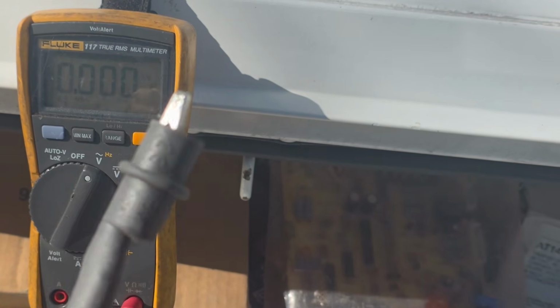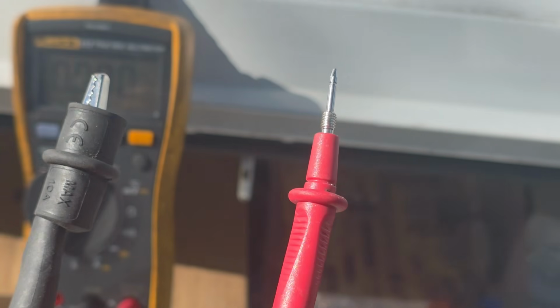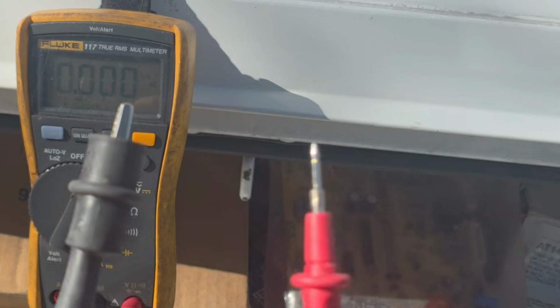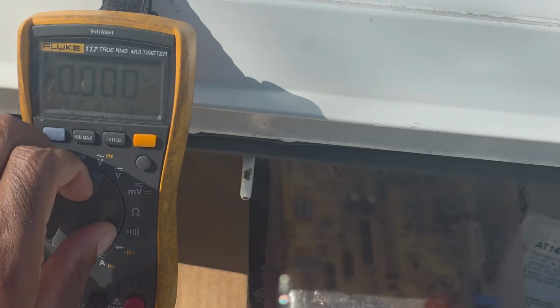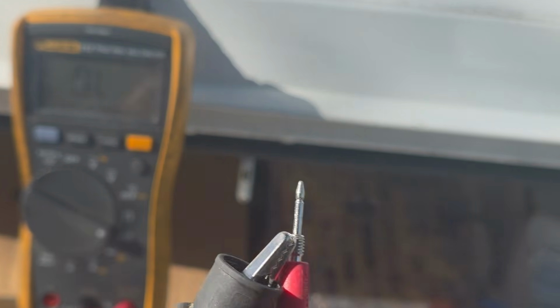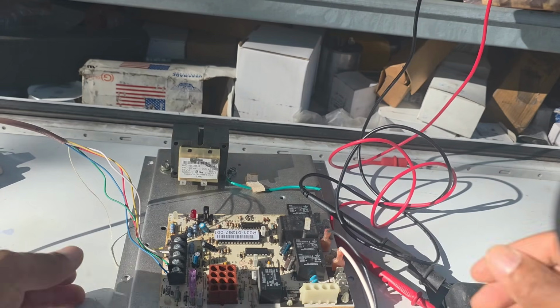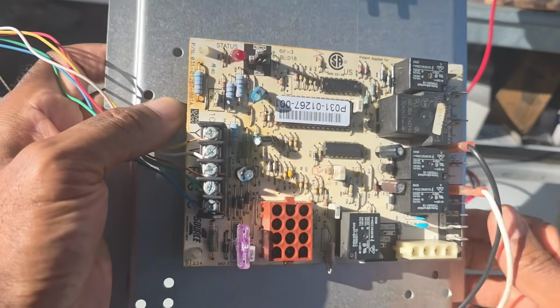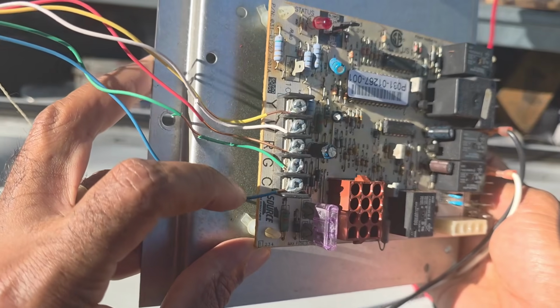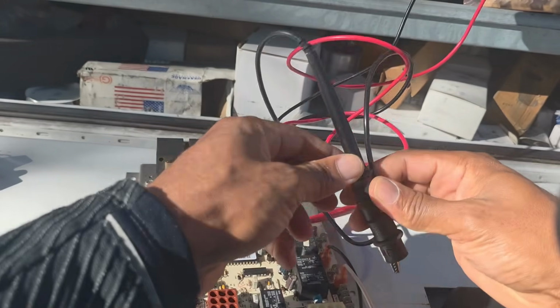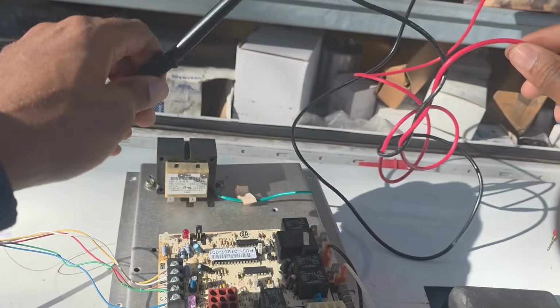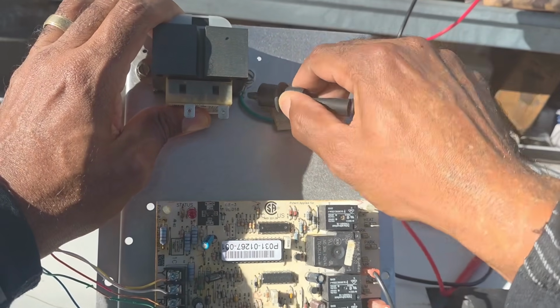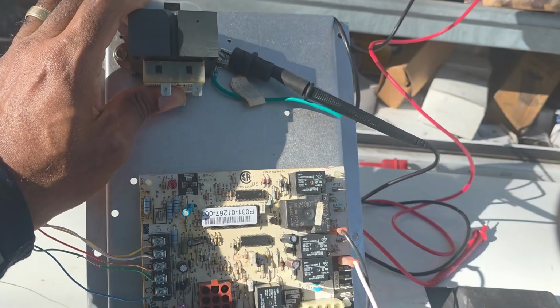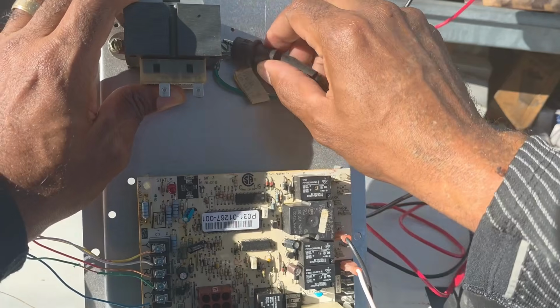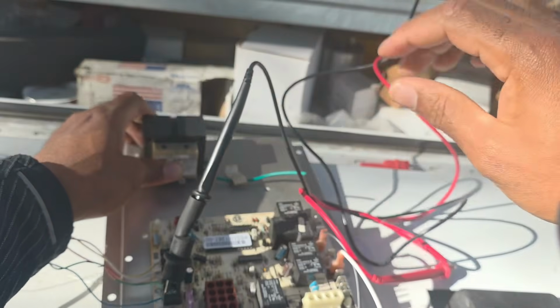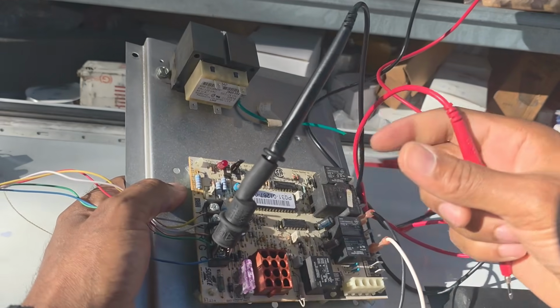All right, so now we have our pivot foot, and we have our lead that we're going to chase the voltage with. To make sure you got good connection, you should get a beep on continuity. All right. So our pivot, you see it says common on the control board. So we're going to put our pivot foot on that common right here. Another point, this could be like a ground right here. If you want to use a ground, there you go. You put that pivot foot on ground. But we're going to be using common, and we're going to go up to the furnace and check it live.